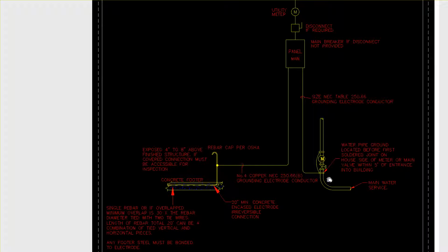This is true of any water system, is we make that connection within 5 feet between the valve and when the water pipe comes into the structure. That's going to be a component of any grounding system in a building that is fed with water, of course. And then there's this jumper across, and you'll see my note here, size per NEC table 250.66, and this is the grounding electrode conductor. And then this is also a grounding electrode conductor going up to pick up the UFER, and 250.66(b) tells us that that doesn't have to exceed number 4 copper. And then when driving ground rods, which I'm not showing here, the ground rods have a number 6 as the maximum required by code. But this is a really basic one-line diagram.